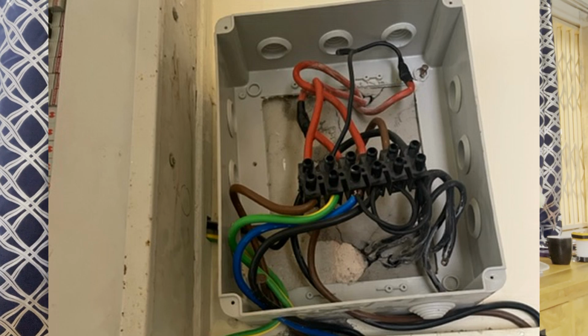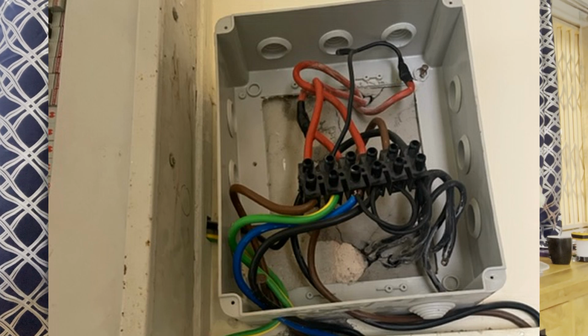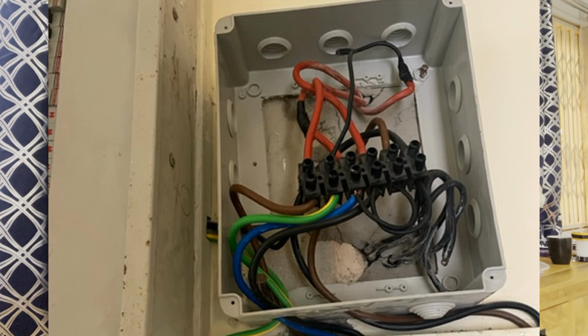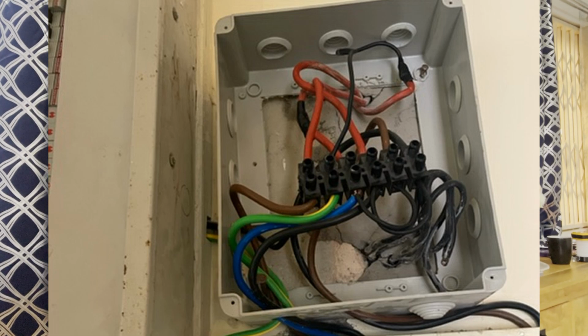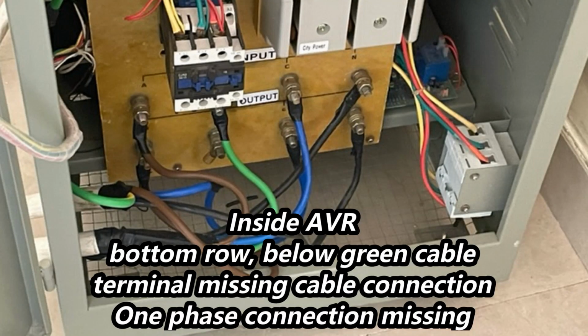Another thing we spotted, the AVR itself is a 3-phase AVR. Okay? But for some reason, the electrician had only wired 2 of the phases. Not sure why. Why would he only wire 2 of the phases? Absolutely doesn't make sense whatsoever. Now that is the reason why the actual AVR display itself was only showing phase 1 significantly as a value and a little bit on phase 3, but phase 2 didn't have anything on it, as in the B phase only had 0.1. That's because simply the AVR was not wired.